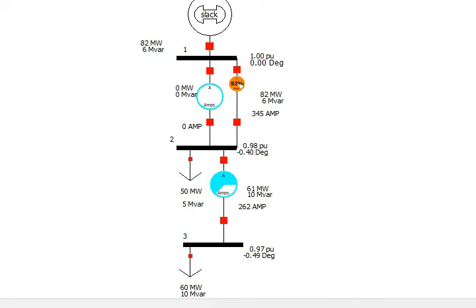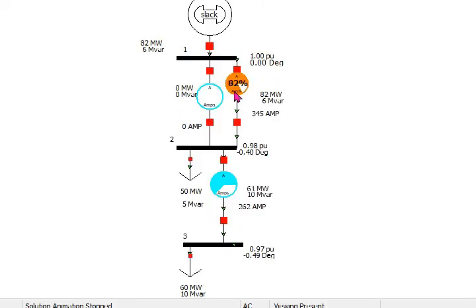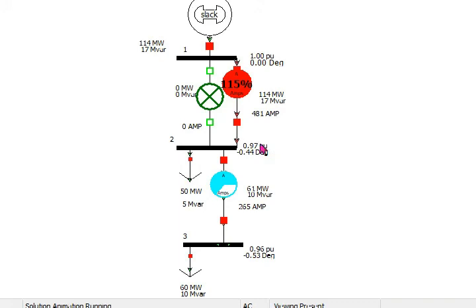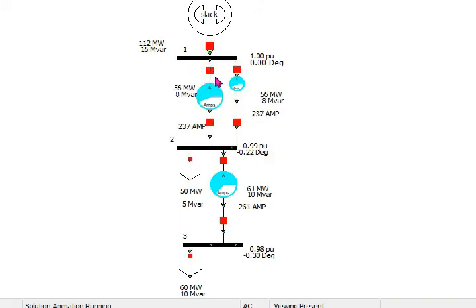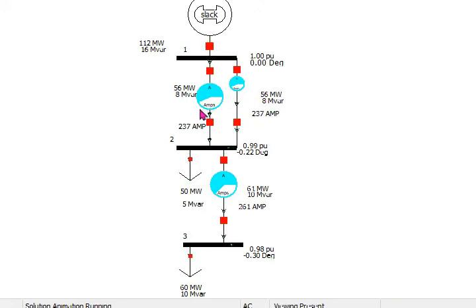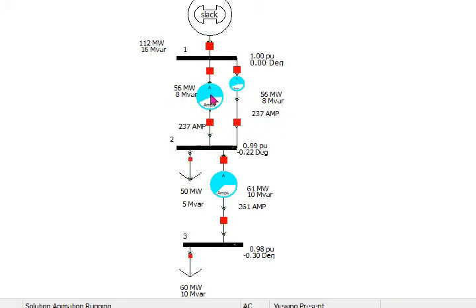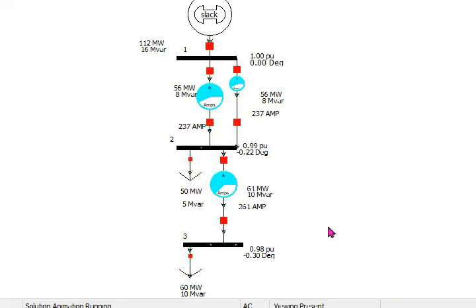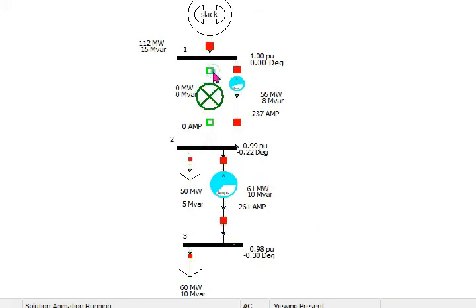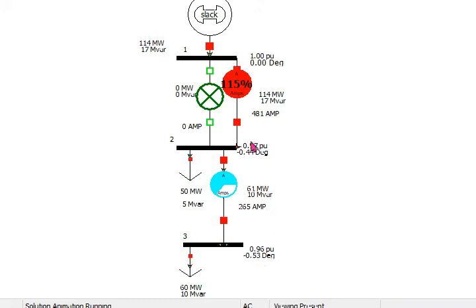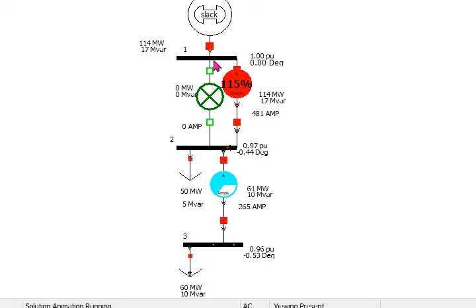So run it. In the previous case it was 115 percent. The loading of the first transmission line is reduced. Previously the current flowing was more than 400 amperes. In this case the current flowing through this transmission line is 237 amperes. Also the voltage in the downward bus is also improved. Thank you.